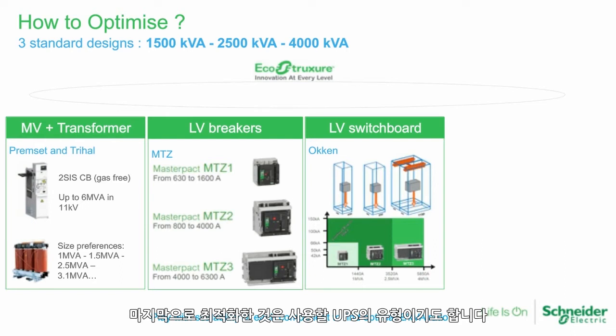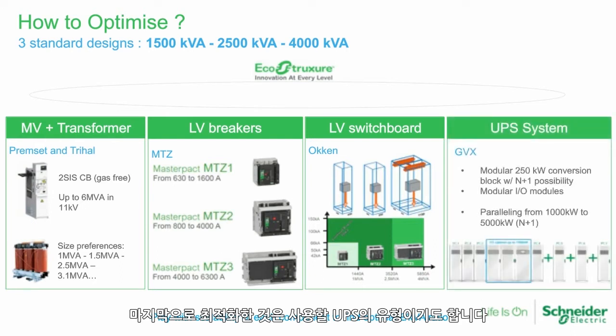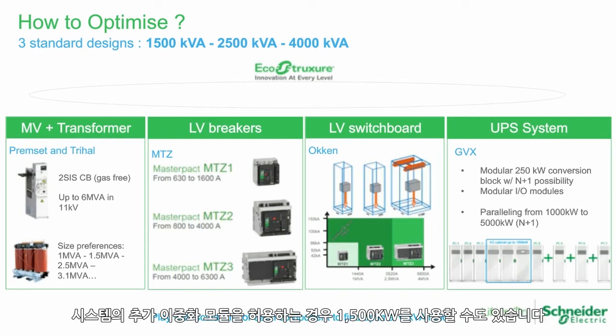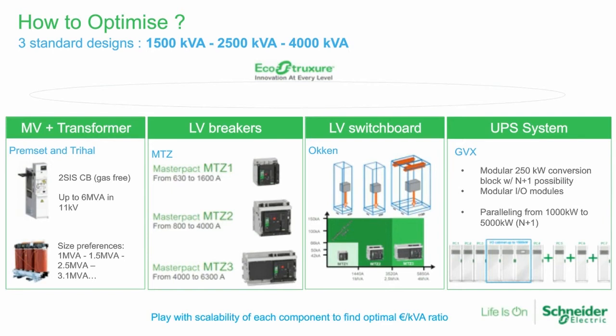So the last thing we have optimized is also the type of UPS to bring. So the sweet spot is about 1,250 kW, and we can parallelize those UPS according to the total power which is needed, especially for the 4000. But at least for the 1500, we can use the 1250, for instance, or even the 1500 with an N+1 module inside to allow an additional redundancy of the system.